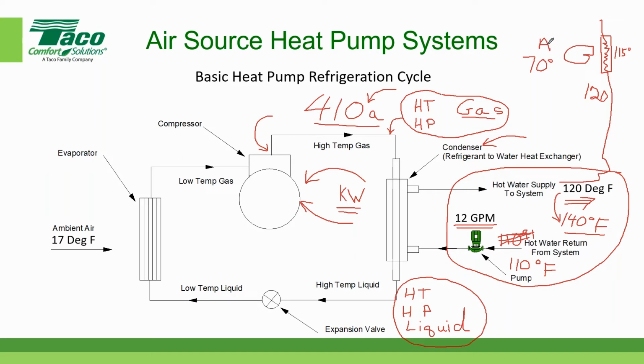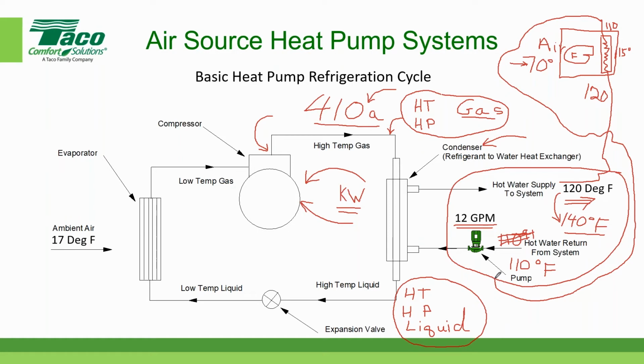Does that make sense? I'm putting this into a fan coil. So there's the fan. I'll label that fan with an F. There's my entering air temperature. And the fan and the coil are inside of a box. And whenever we put them inside of a box, we call them fan coils. Okay, so that water temperature has gone from 120 now down to 110 because I've given up heat into the space, and now I'm bringing that piping system all the way back. This is not the best way to pipe something, but yeah, don't try this at home. This is that old expression: if you're going to build a piping system, don't build it this way. But I just took a picture of that and sent it to my contractor for a quote.